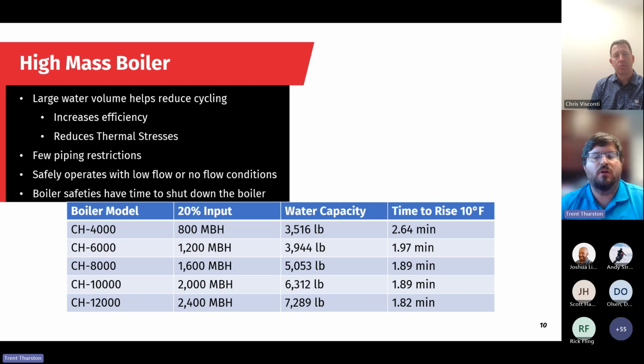Another aspect of being a high mass boiler is we do not require a dedicated boiler circulating pump. We can use a variable primary system. Now, if the end user does prefer a primary secondary system, we have no restrictions there. They're perfectly fine to use a primary secondary, but we have this added flexibility. Finally, we have the ability to safely shut down in case there is a no flow condition. Now, if there's a no flow condition, obviously no heat's going out of the boiler, so it's not producing useful energy for us. But due to our large water volume, even if there's a system failure that causes a no flow condition, the temperature will rise slowly, but enough time so the boiler's high temperature safeties shut the burner off, and we still have a safe operation.